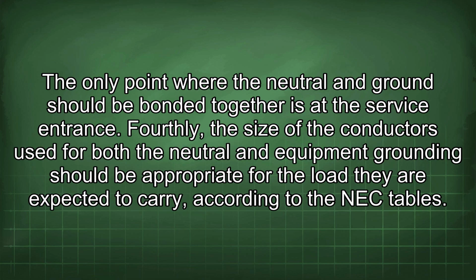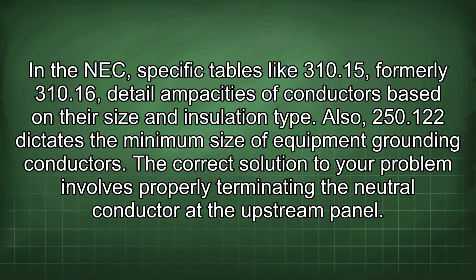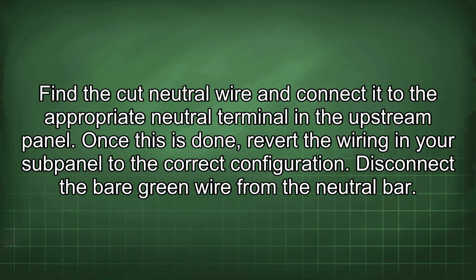Fourthly, the size of the conductors used for both the neutral and equipment grounding should be appropriate for the load they are expected to carry, according to the NEC tables. In the NEC, specific tables like 310.15, formerly 310.16, detail ampacities of conductors based on their size and insulation type. Also, 250.122 dictates the minimum size of equipment grounding conductors. The correct solution to your problem involves properly terminating the neutral conductor at the upstream panel. Find the cut neutral wire and connect it to the appropriate neutral terminal in the upstream panel. Once this is done, revert the wiring in your subpanel to the correct configuration.